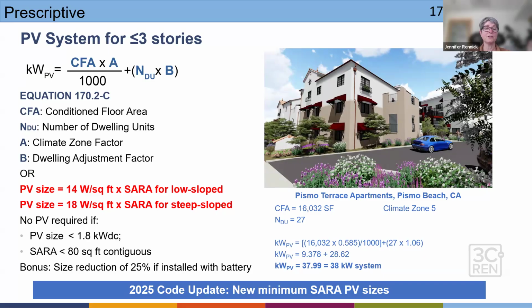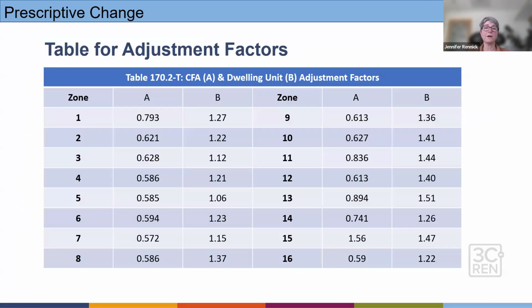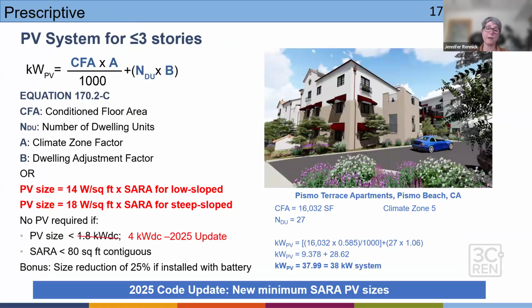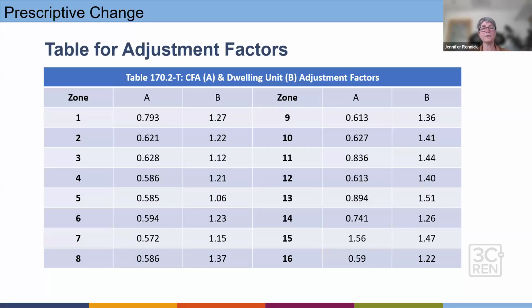The other change is that if you had a PV system size less than 1.8 kilowatts DC, you could be exempt, but they've upped that to 4 kilowatts DC for the 2025 code update, which is consistent with the high rise. Okay. So now when we go back up, there are tables for factor A for your climate zone and factor B for your dwelling adjustment factor. And I put this table here for your reference so you could have it together.